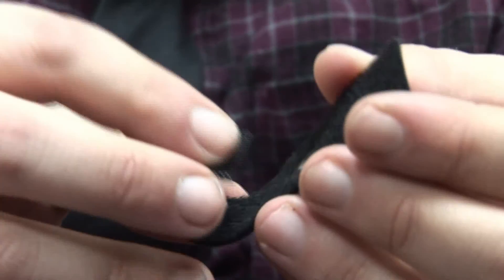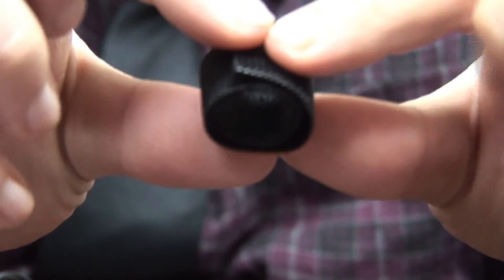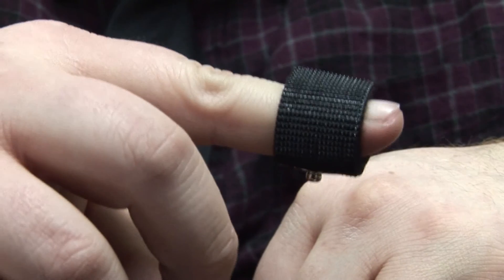As a quick tip, a mistake that a lot of people make is they pre-roll the Velcro before sliding the finger in. What that's going to do is overlap the metal contact and separate the finger from the metal contact. In order to get a good reading, your skin needs to remain in contact with that metal at all times. Now you're all hooked up and you should be ready to measure GSR.